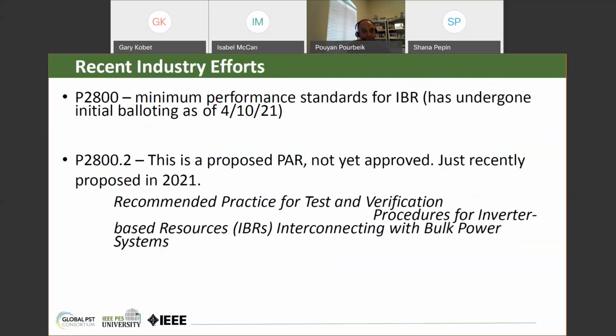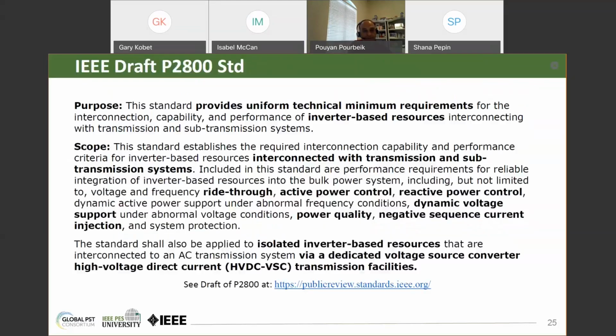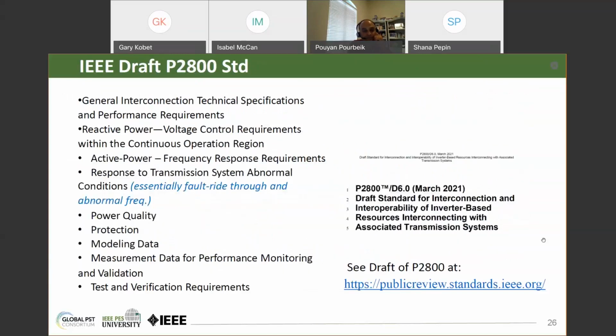There is also a proposal for a new PAR, for a new proposed standard. So this is just a proposal right now to look at recommended practice for testing and verification of inverter-based resources. If we go to the next slide, just a high-level mention of what the P2800 standard is on. I'm not going to read all this. I'll leave that for people to read later. This is what the standard covers. And again, it's a draft standard. It's not yet an approved standard. It's just gone through initial balloting. And there are hundreds of comments which will have to be addressed.